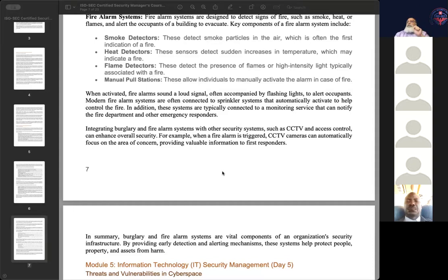You're not able to put it in an area that has 200 Celsius degrees, because there it's already burning the area, but they have a temperature at which they operate that can be high. It's not necessary to be normal. And then it will not give you alarm, but if the temperature goes high very fast, it will give you alarm, okay? So it's a useful sensor to know, the heat detectors.